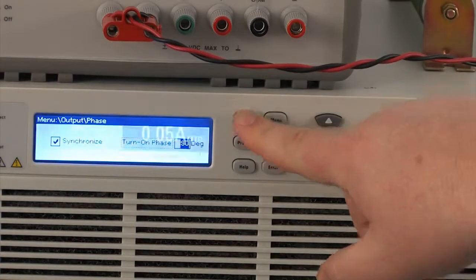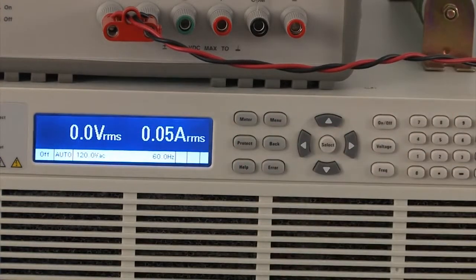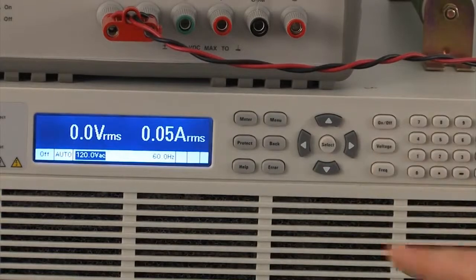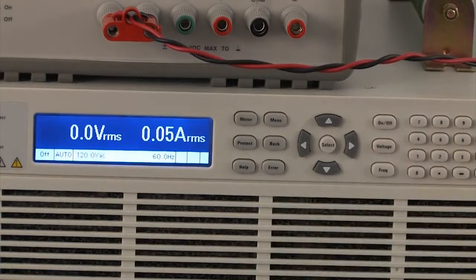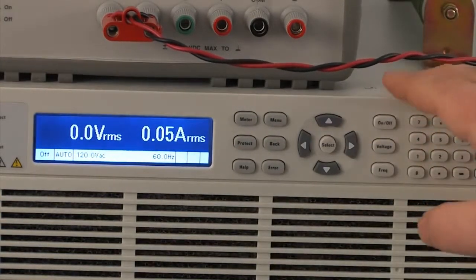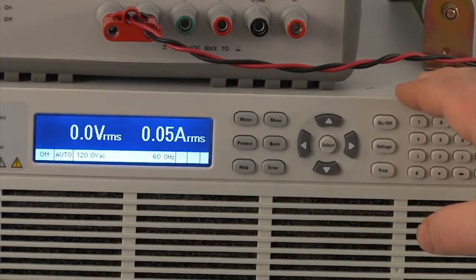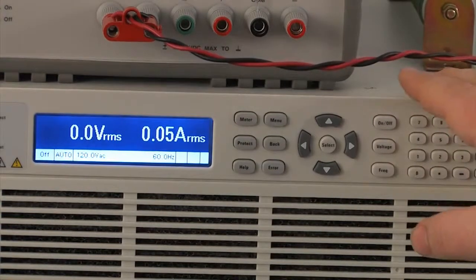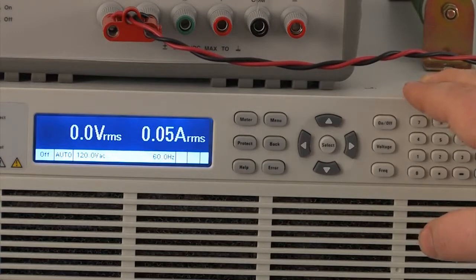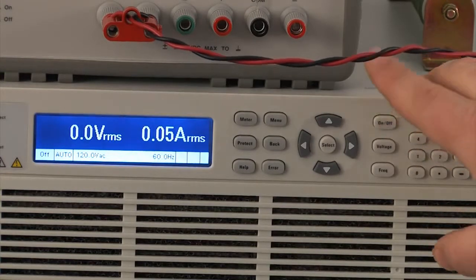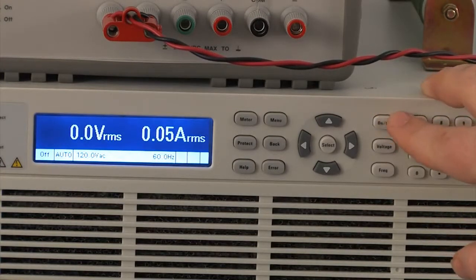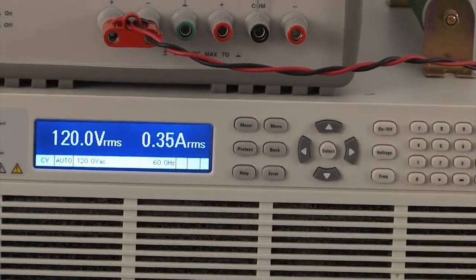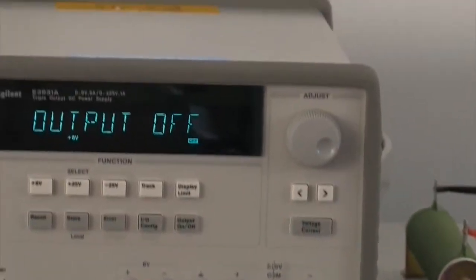So we're going to go back to the meter. So we're back in our standard view. The output's off. We're going to make sure our voltage is right. Our voltage is set to 120 which is what we want here and when we hit the output on off button it's going to turn the AC source on at 90 degrees of phase in the AC output waveform and then turn our power supply on. So turn on. You can see our power supply turned on here.